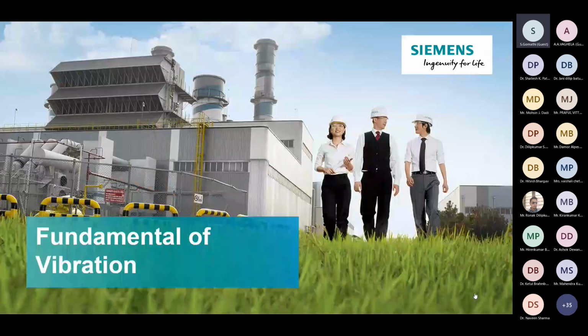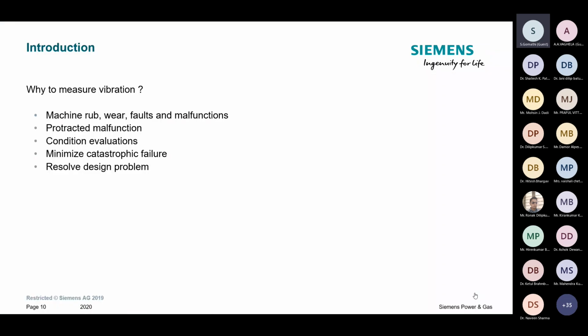I think we need not cover the fundamentals of vibrations here. Normally, why do we need to measure vibrations? I touched upon this in my last presentation also—rotary machines typically we don't want to fail. We want to measure it and run it continuously, generating electricity or making money for the power plant, and we don't want to stop it because of vibration issues. And if vibrations are there, it's because the rotor, blades, and casings have very little clearance.